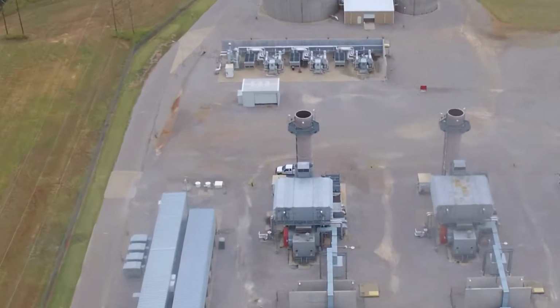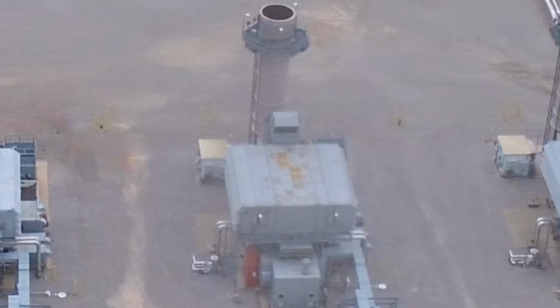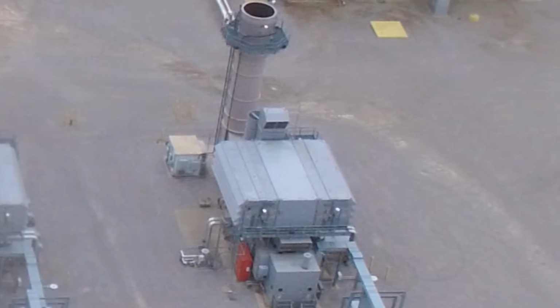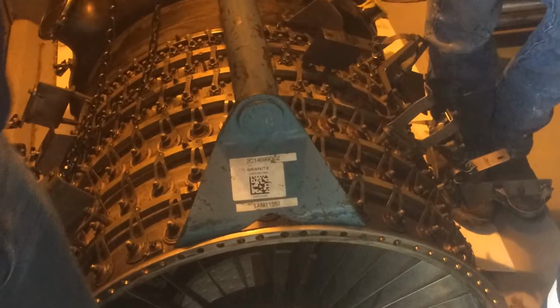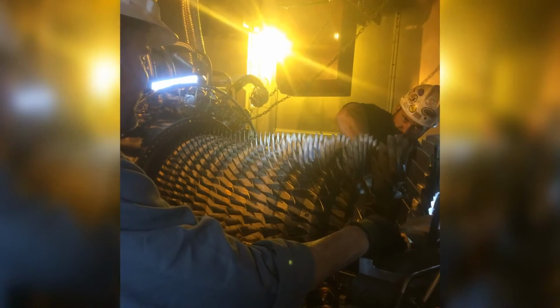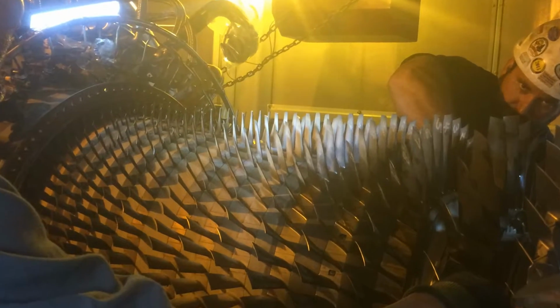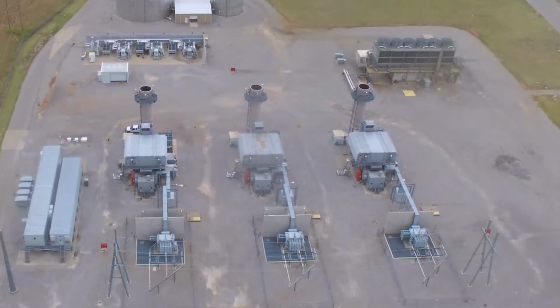During the annual inspection outages of the LM6000 units at the Anadarko plant, a few maintenance opportunities arose. Anadarko Unit 10 was found to have indications of potential failures of high-pressure compressor stages 3 through 5. Technicians from GE and the plant mechanics were able to change out the compressor blades in 3 12-hour shifts. The compressor work was completed all while the machine was inside the package.